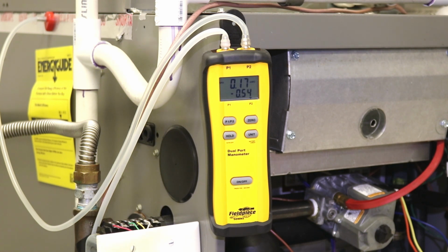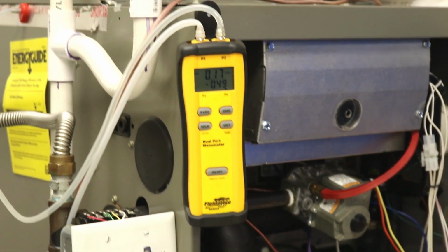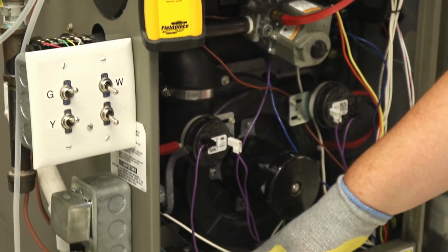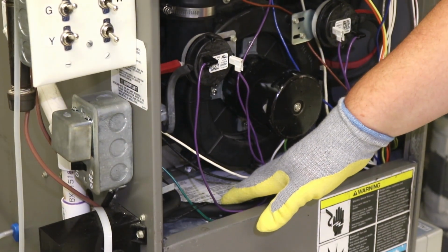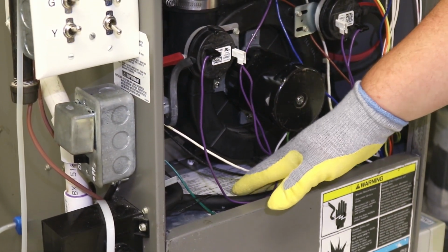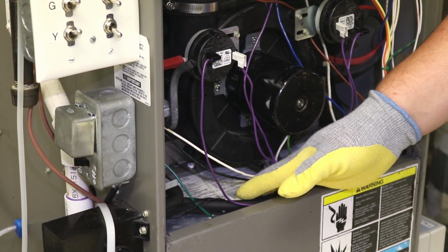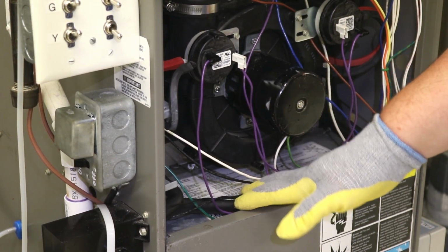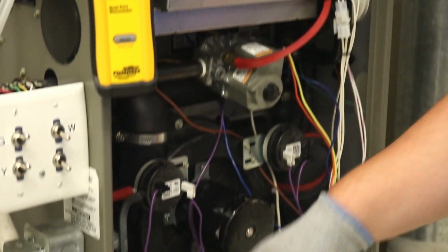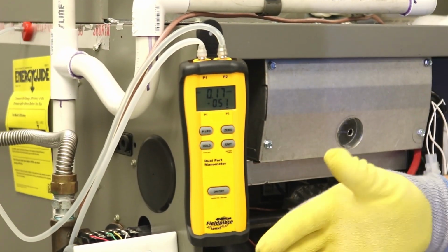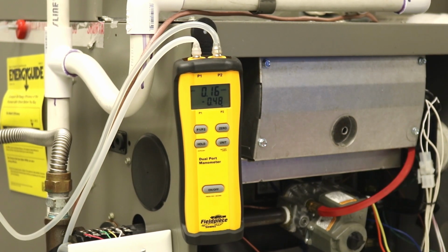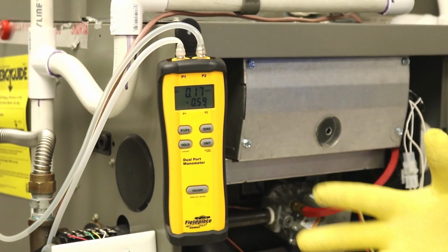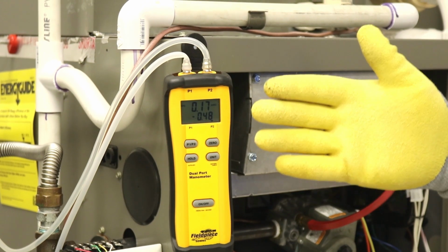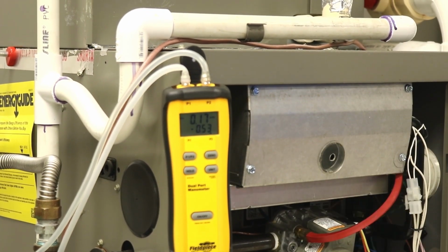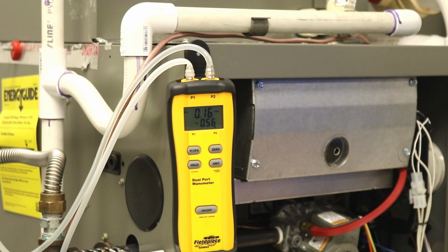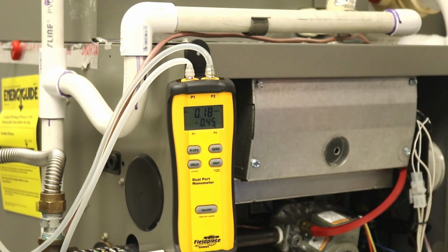inches of water column. You can always find on the equipment from the data plate down here at the bottom, it's going to tell you what the maximum static pressure is for that system. For this particular system, I've taken the liberty of going ahead and checking that out. It is 0.5 inches of water column. So if this number on our manometer were above 0.5 inches of water column, we know that we have an airflow issue. So as you're looking at the system, make sure as it's running, while the equipment is at full bore, that you're not going above that 0.5.